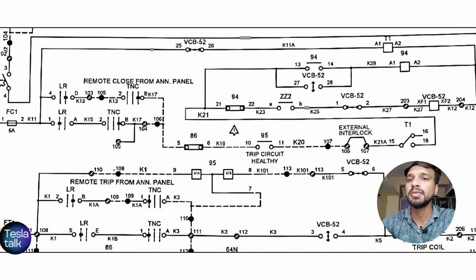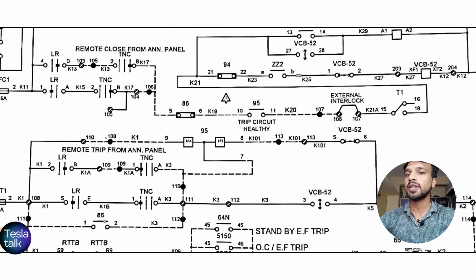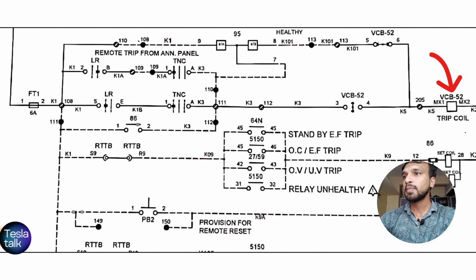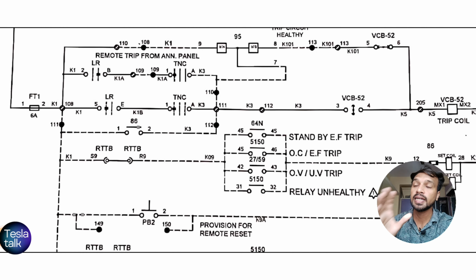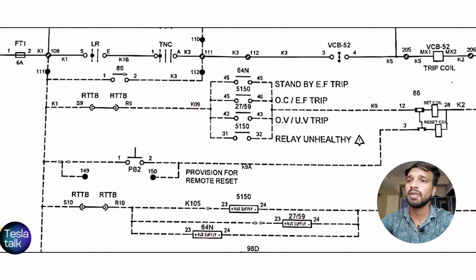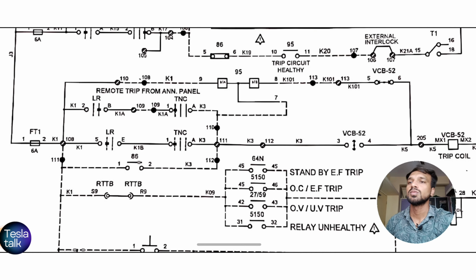There are also some elements used like the ZZ switch and the 95 trip circuit healthy contact. It's a NO contact. So 95 is the trip circuit healthy indication. So we will see the tripping circuit now. The tripping circuit is responsible for opening the breaker when there is a fault or when a trip signal is received. The remote trip command comes from the same annunciator panel. You can see here, the same annunciator panel sends the command to close and trip the breaker.